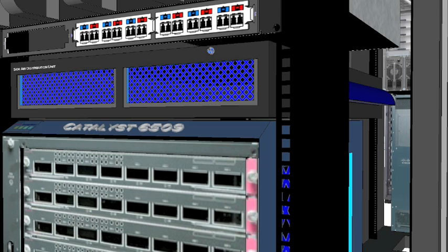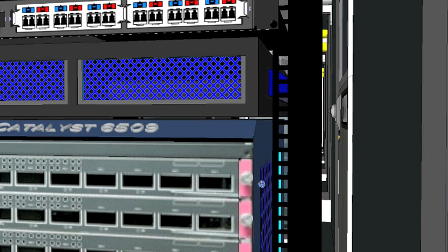Many people don't realize, but we do front to back options for most of our switches, and for ones that go right to left, we have partners that make specialized cooling systems like this one, the side air distribution unit made by APC. What this does is it sucks cold air off the front, blows it through a hood down the side to the inlet of the switch, and ensures that your airflow stays consistent from rack to rack by passively redirecting the exhaust to front to back.